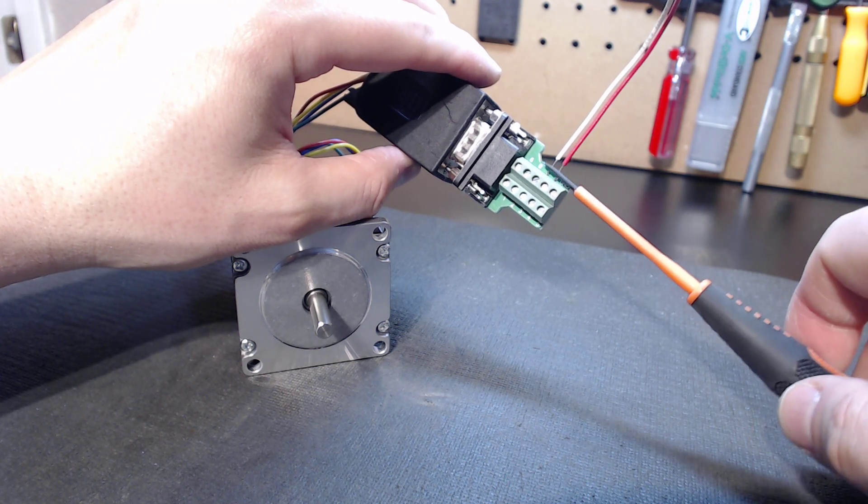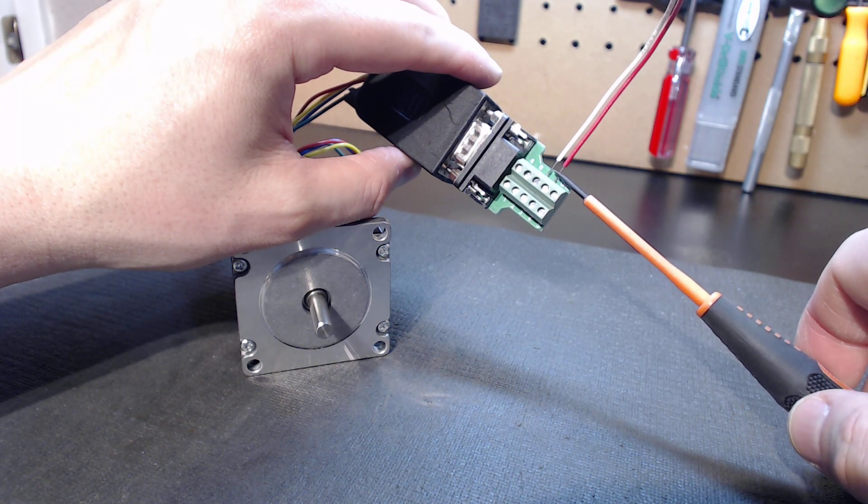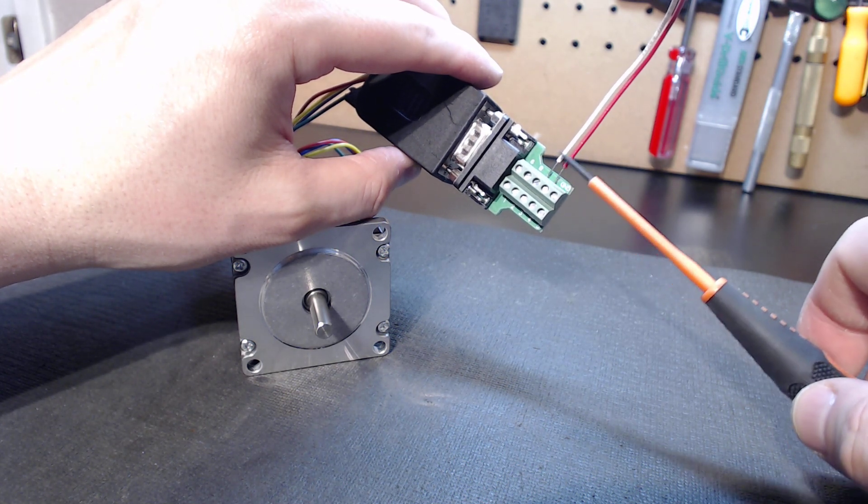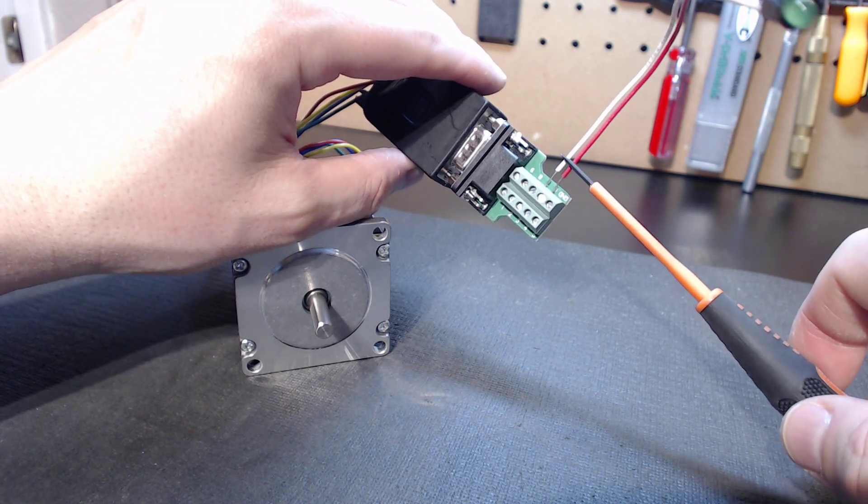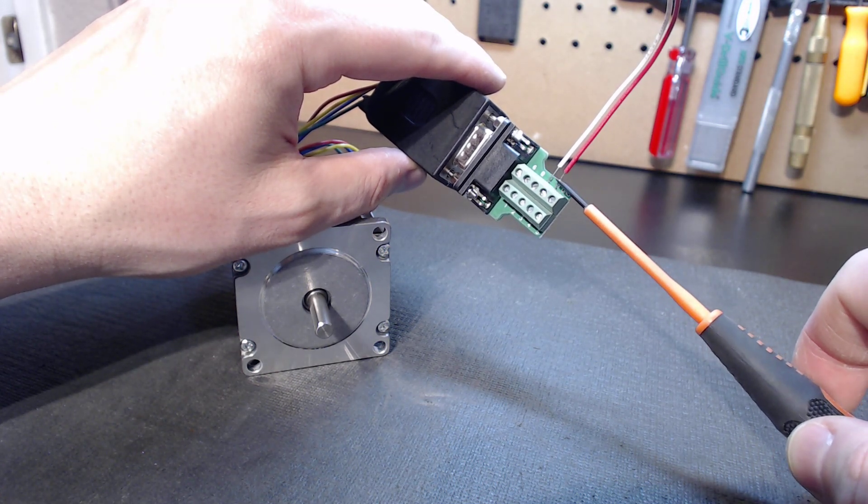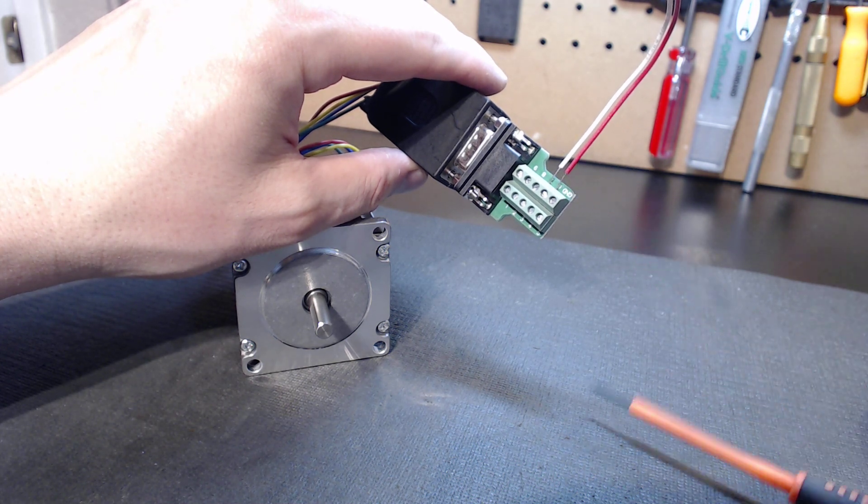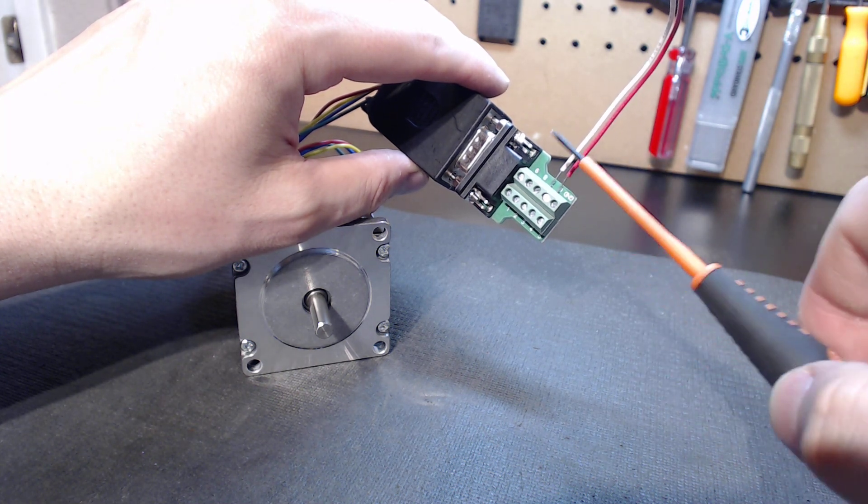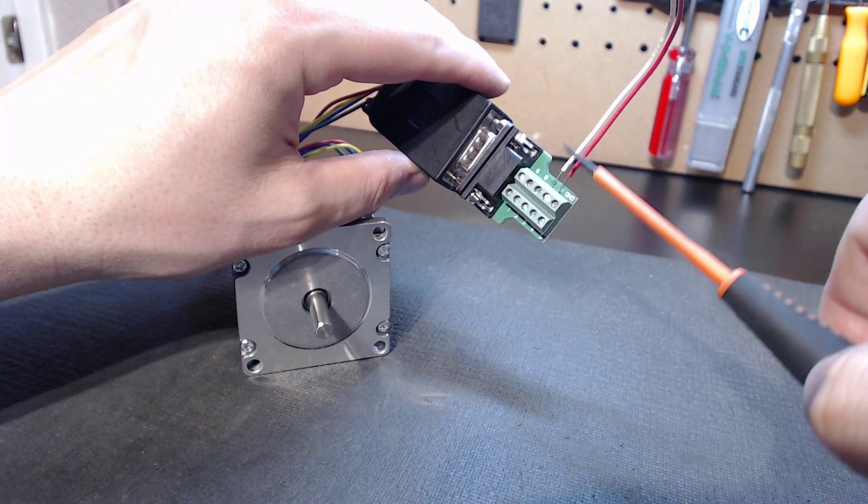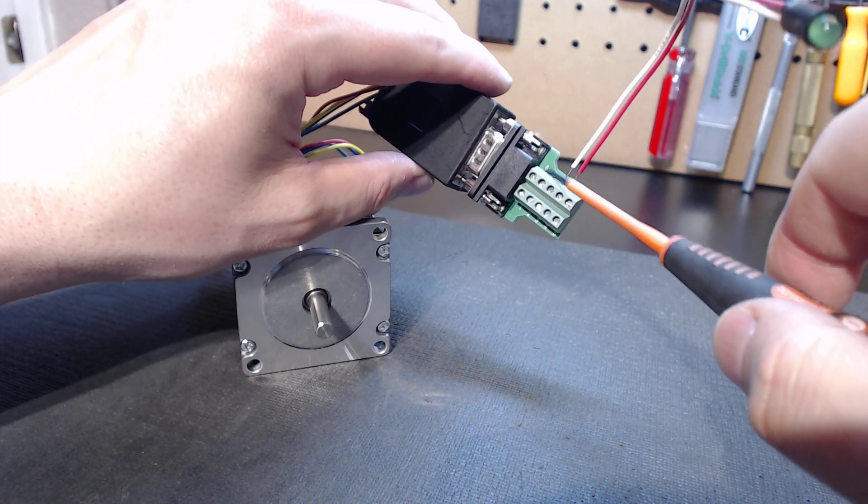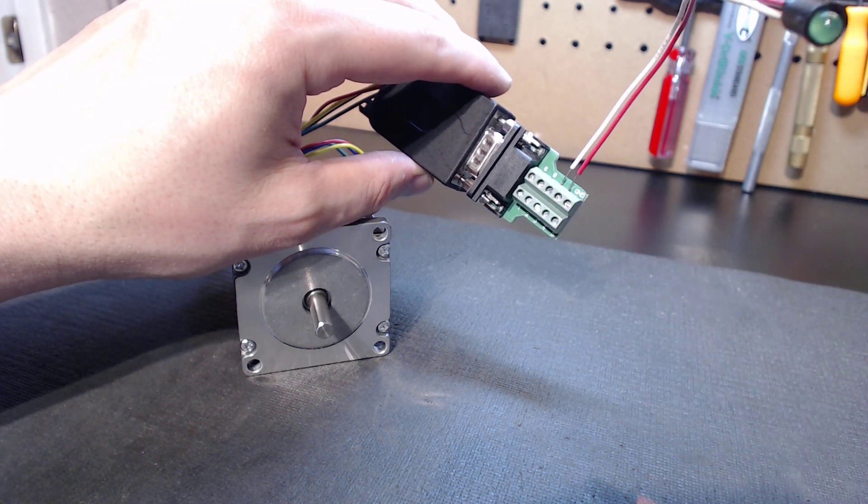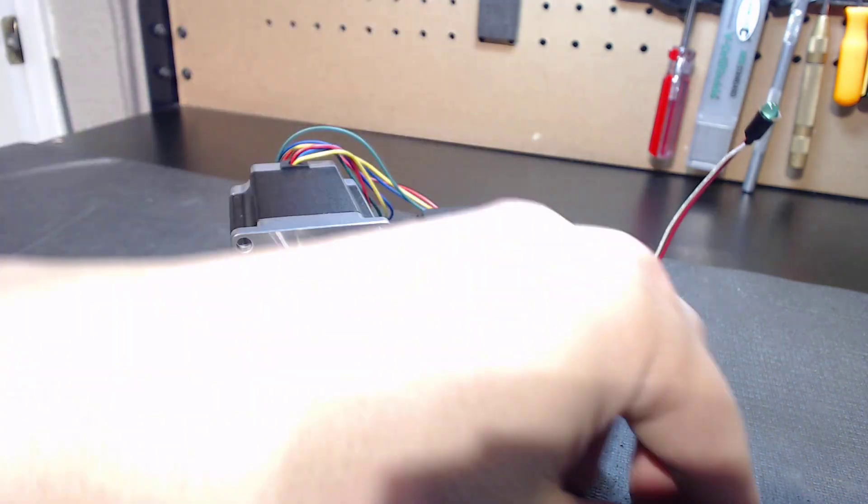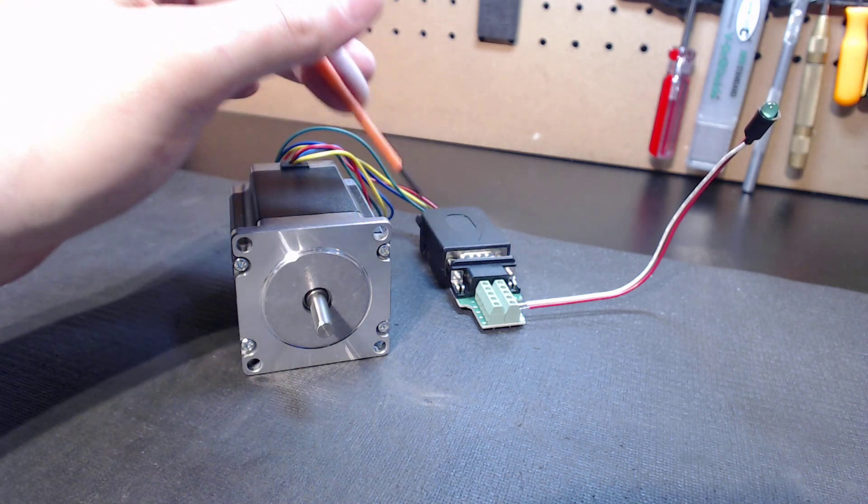Okay, now we don't know if this is A or B polarity but we do know that it is an A plus and A minus or a B plus B minus. Worst case scenario, if we connected this to a drive now, as long as we select either a B plus B minus or A plus A minus and connect it congruently - meaning that we don't mix it. So if I select B for instance, I want to connect these two. I would just pick a wire or pick a lead and say okay I'm going to make red B plus and then I'll make white B minus, you're fine. If I reverse that and say I'll make red B minus and white B plus, that's fine. But I cannot mix a lead from here from B to an A. And we know that eight and nine, being this is a bipolar motor, we know eight and nine is definitely going to be an A polarity. If we did that and connected it to a drive, you would blow a drive.